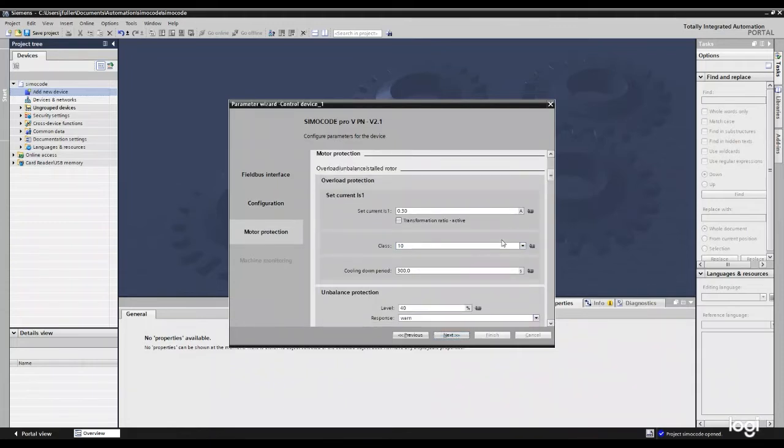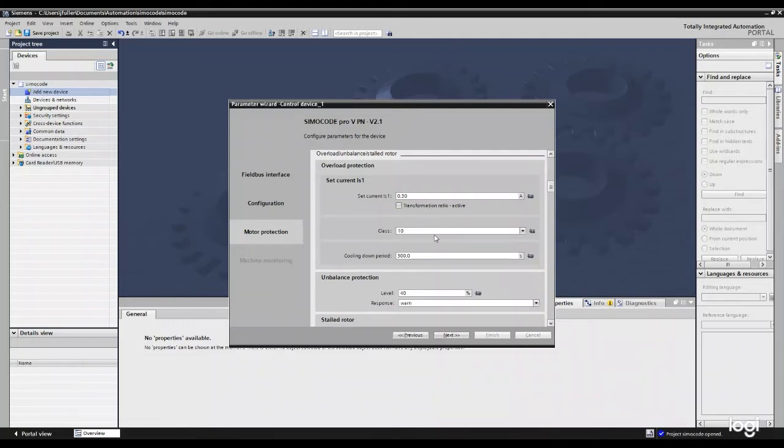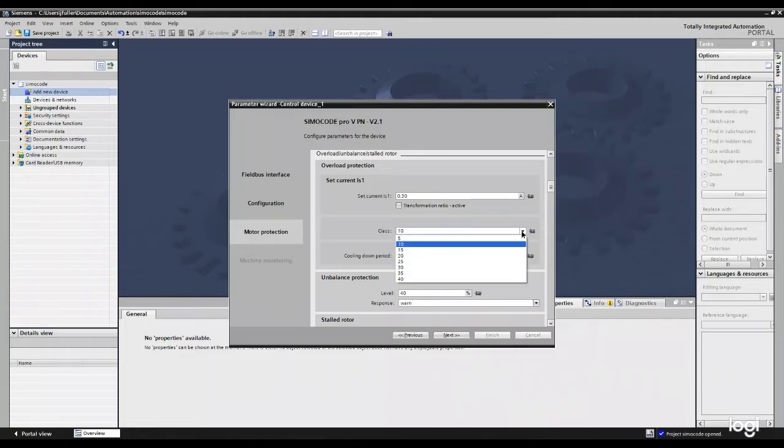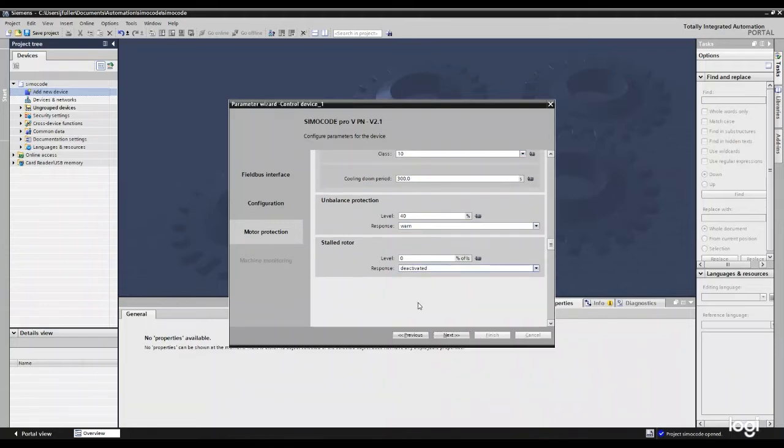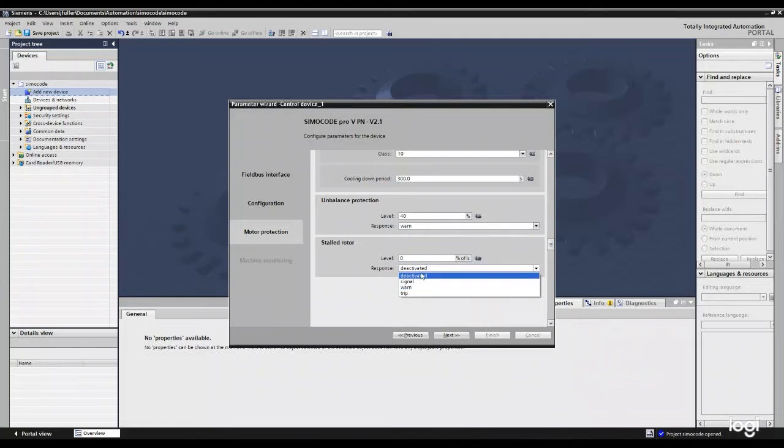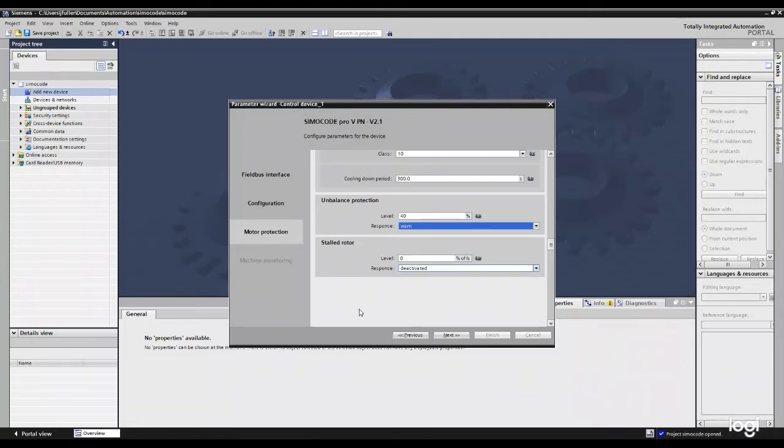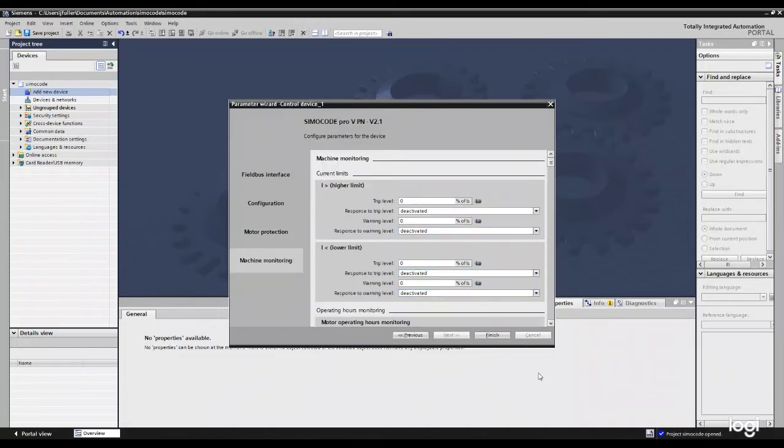And this is where our motor nameplate data is going to come in handy. So we're going to have our different current here. What are we looking at? What overload class we want? You see, we got some drop downs. And then we've also got some other protections like a stalled rotor. We can set it to signal warn or trip. Same with our unbalanced protection. So we're just going to leave that. Click next.